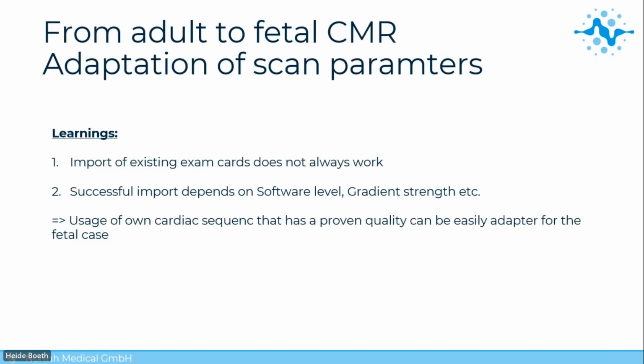And if you go one step further, we had a big learning regarding the exam cards, because normally we have them on our website so you can download them, for example, for Philips. But this doesn't work all the time. If we export one exam card, even if the software version is quite similar, and then import it, sometimes the MR images look like the first MR images ever, which is sometimes related to different gradient strengths or slightly different hardware. But what we experienced is that if you use the standard sequence from the vendor, for example from the vendor folder from Philips, Siemens, or GE, then it works quite fine. Or you use your cardiac sequence that you use for adults and just adapt some parameters.